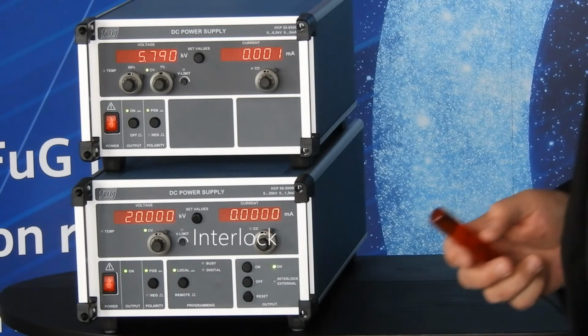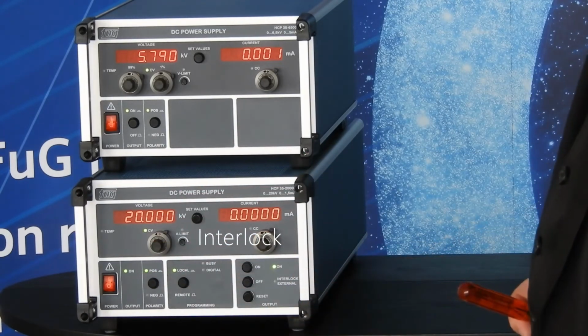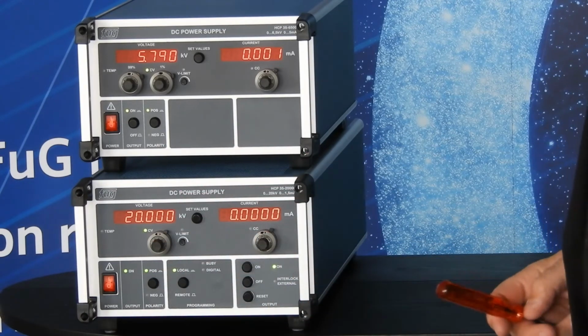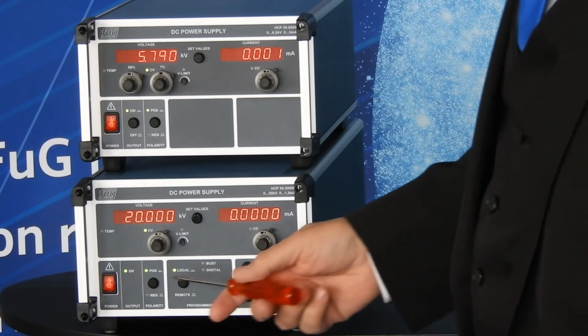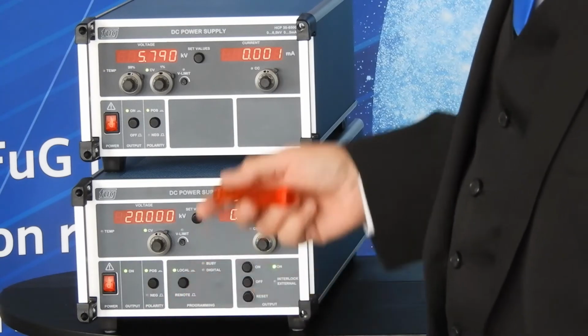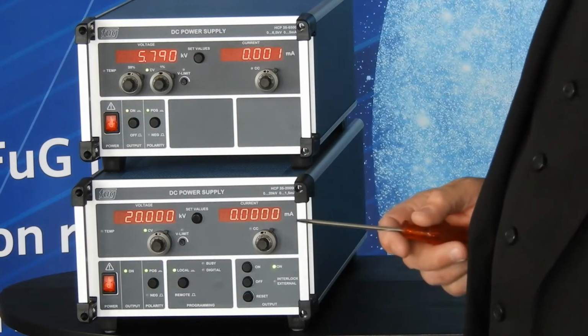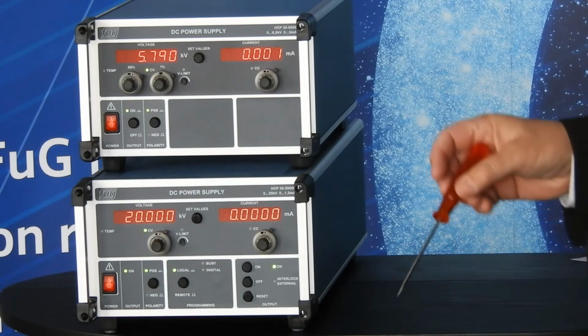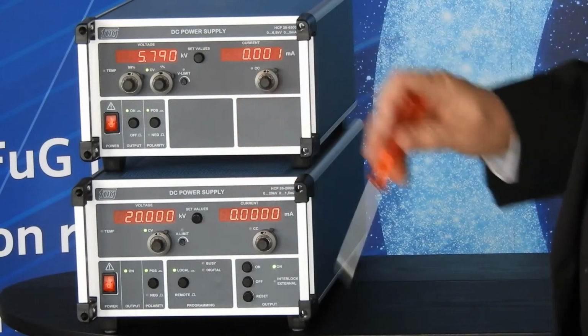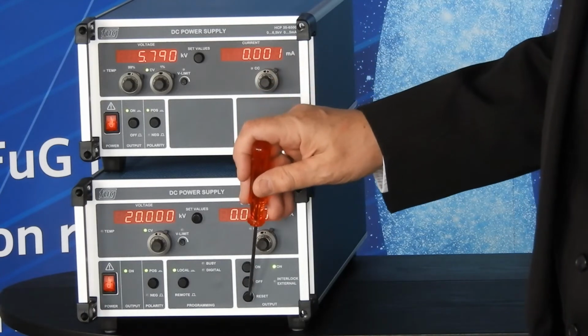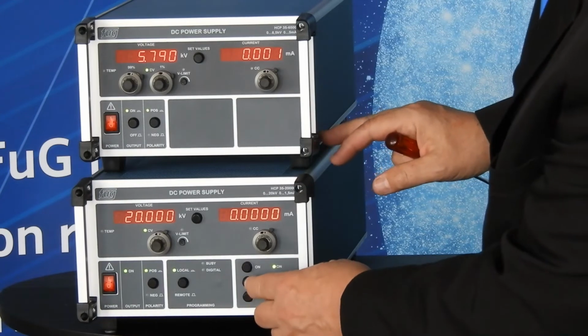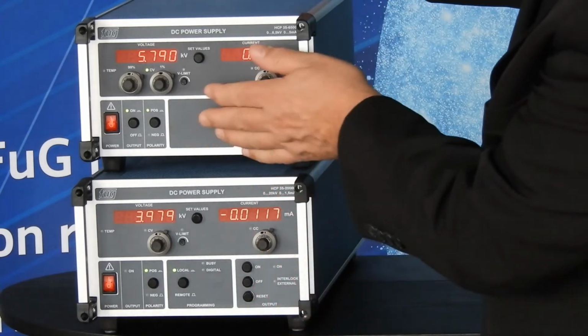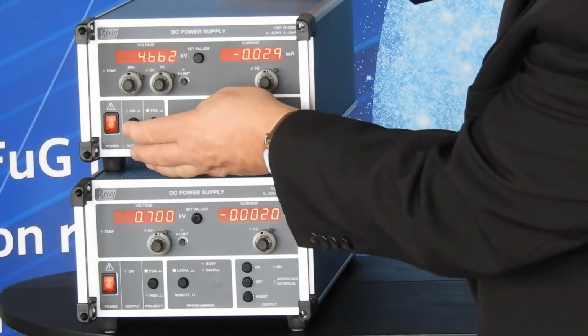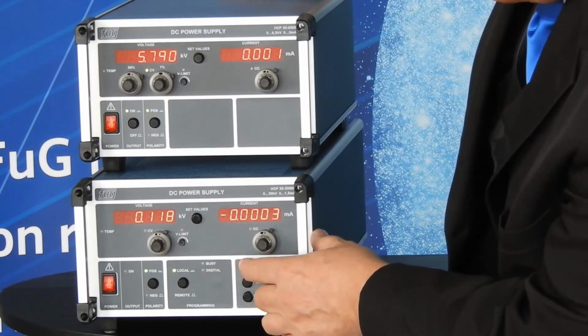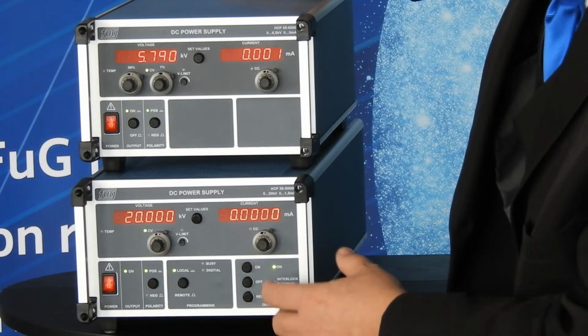A further feature, which we have on the power supply at the bottom, is the so-called interlock feature. You see that this power supply doesn't have the on-off button that the power supply on top has, which is the usual way to switch the output on and off. Instead, this power supply has three buttons on the right side: one is on, one is off, and one is reset. The on and off functions are nearly the same as for the power supply above. The on button switches it on, and pushing the off button switches it off, and the voltage runs down.